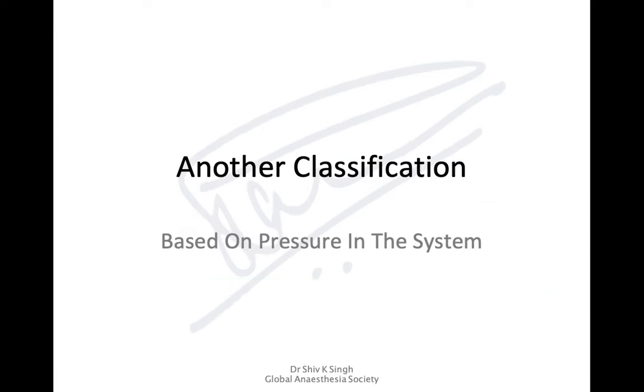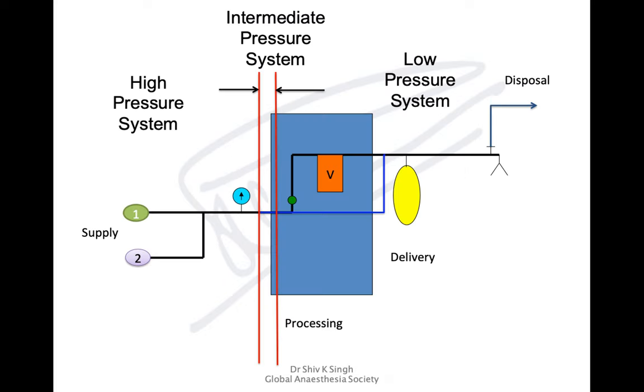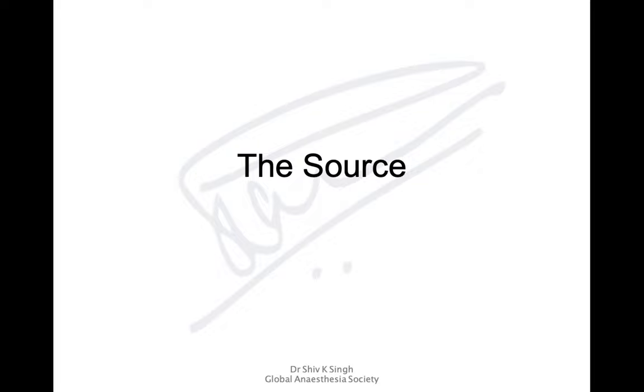There's another classification based on pressure within the system. The high-pressure system includes the VIE pipelines and cylinders. The intermediate-pressure system includes the second-stage regulator. The low-pressure system starts from the flow meters onwards to the patient end.